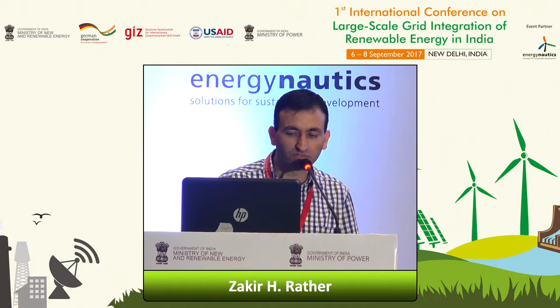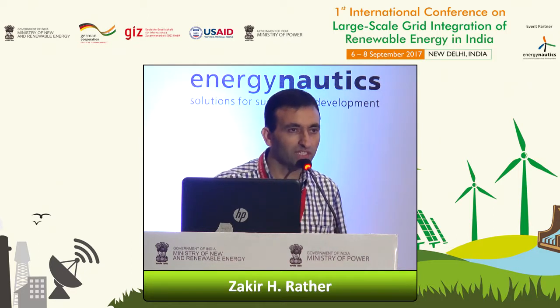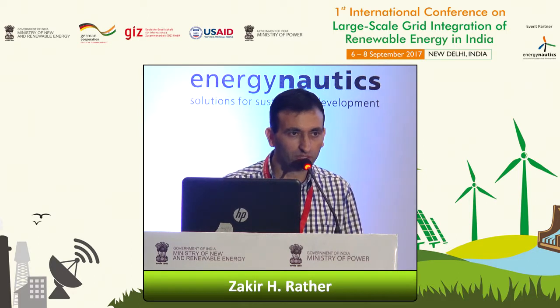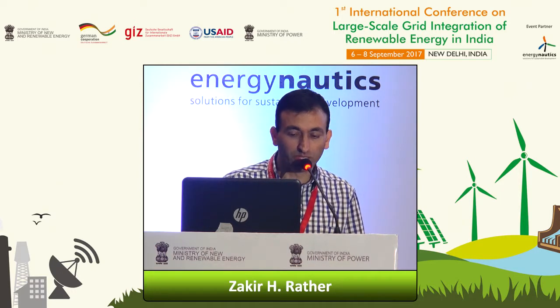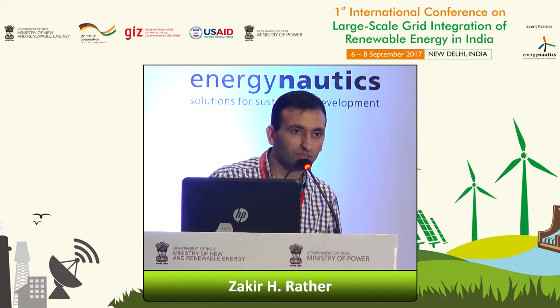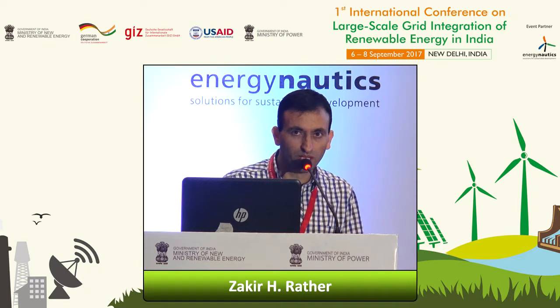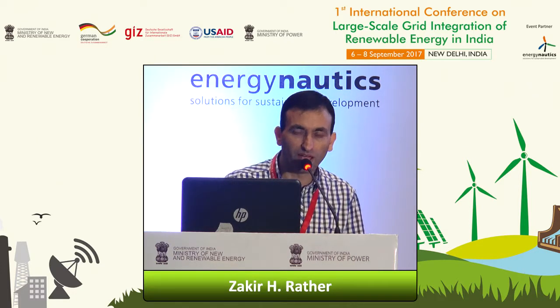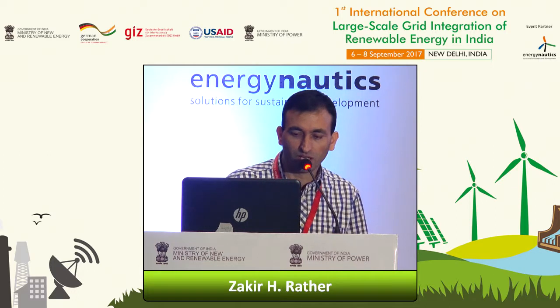In the next case, we activated only the inertial response from the wind turbines, and the droop response was not activated. So there was no additional frequency support except the inertial support from wind turbines and wind farms. The penetration level was again 75%. What we saw is that the nadir was improved compared to the previous base case where we didn't have inertial response. As expected, the nadir was improved by having this inertial response from the wind turbines.